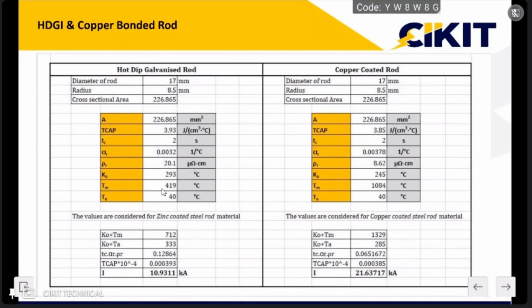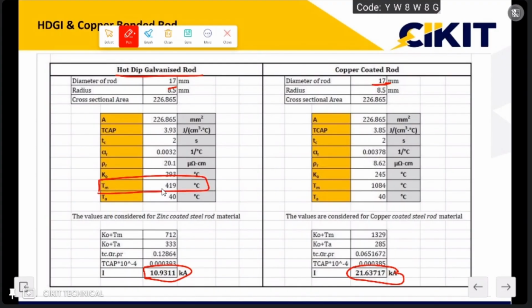If I'm taking this hot dip galvanized rod of 17 mm dia, the current carrying capacity is around 10.9 kiloamps. Whereas for the same 17 mm dia copper coated rod, the current carrying capacity will be around 21 kiloamps. So the current carrying capacity is almost double. The main parameter which makes a difference is the fusing temperature.